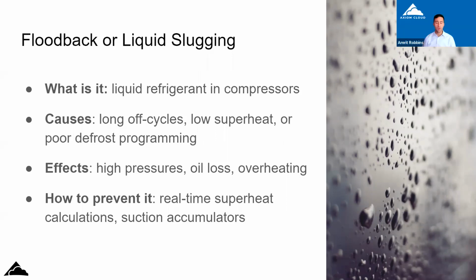Can you talk about the difference between total superheat and the superheat in the suction header? Yeah, so the total superheat is usually read at the system. You read it at the EPR or whatever device is at the rack, suction stop, whatever it might be. You take superheat at the header for that circuit, and you can go across the whole header. And if they're all within, let's say, 20 degrees total superheat, but you've got lower at the header, something weird might be happening.